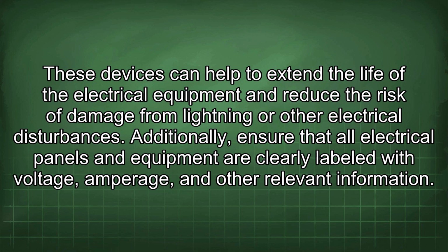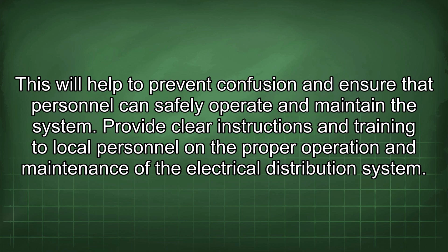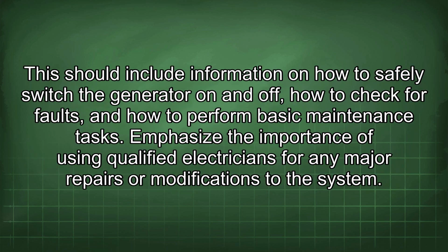Additionally, ensure that all electrical panels and equipment are clearly labeled with voltage, amperage, and other relevant information. This will help to prevent confusion and ensure that personnel can safely operate and maintain the system. Provide clear instructions and training to local personnel on the proper operation and maintenance of the electrical distribution system. This should include information on how to safely switch the generator on and off, how to check for faults, and how to perform basic maintenance tasks. Emphasize the importance of using qualified electricians for any major repairs or modifications to the system.